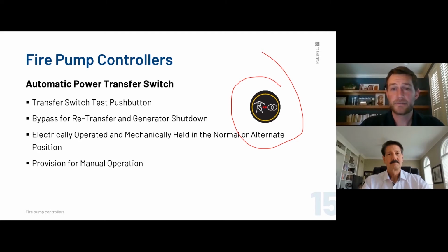What this button is not to be used for is while you're flowing water. If you're flowing water on normal power and you try and press this button, nothing is going to happen. The way that we would recommend testing under flowing conditions for switching over to alternate power would be to actually kill power. So kill the power on the normal power side, which will simulate a power loss. Send the signal to start the generator. Everything will start back up, and everything will transfer over. And that's how you can run that flow test in that scenario. But this button is not used for that. It's strictly for exercising the generator and the transfer switch.